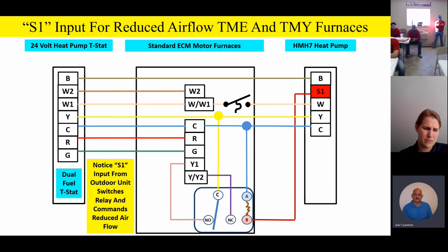Now, guys, the reason we recommend these kits, I want to make something clear. We recommend the kit because of the supplied parts. It comes with a biflow filter dryer. It comes with the little relay kit. It also comes with some pre-made harnessing. Now, we had a contractor a while back make a comment, well, you know, I've got biflow filter dryers on my truck, and I've got peanut relays on my truck, and I've got low voltage wire that I can make up myself. Can I make up my own relays, and can I make up my own kit? Well, of course you can. And you know, if you want to just take a little peanut relay and hook up some 24-volt wires yourself, make up your own little wiring, and put your own biflow filter dryer on there, let her rip, no big deal.